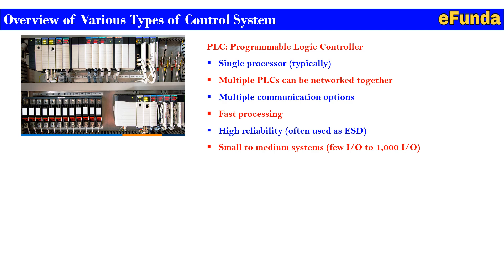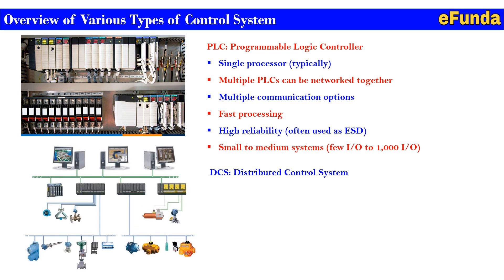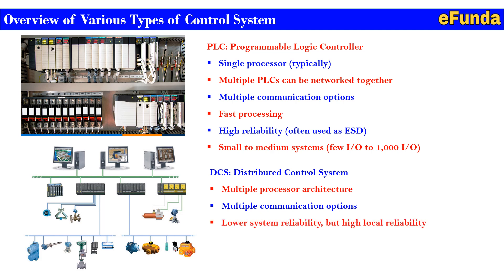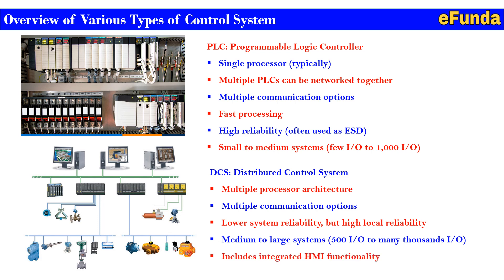The second type is the Distributed Control System, DCS. One can refer to the picture showing the architecture, which includes mainly multiple processor architecture, multiple communication options, and lower overall system reliability but high local reliability. It is a medium to large system — from 500 IOs to many thousands of IOs — and includes integrated HMI functionality.